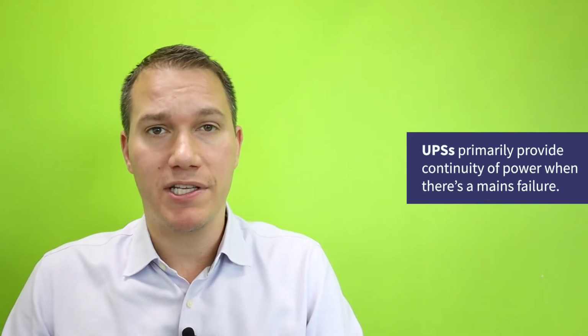UPSs are there primarily to provide continuity of power when there's a mains failure. Within data centers, and certainly those that have generators, they provide continuity of power until the generator can get up to full speed and take over from the mains electricity. Within a server room configuration, if you don't already have a generator in place, UPSs will typically be spec'd to run for up to 30 minutes, which normally gives a server administrator time to log in and gracefully shut down any servers.